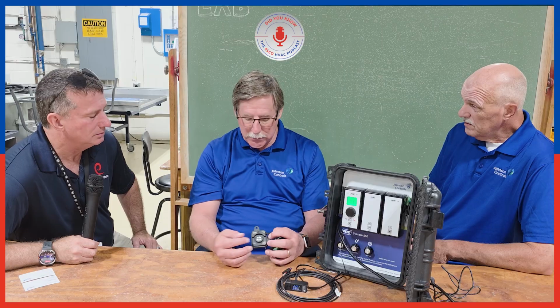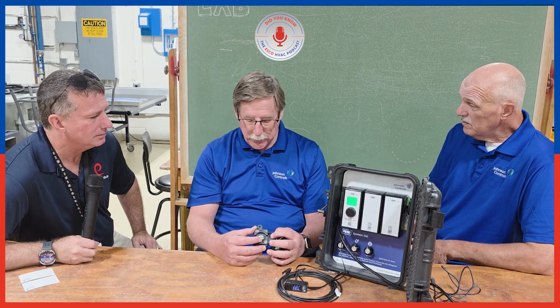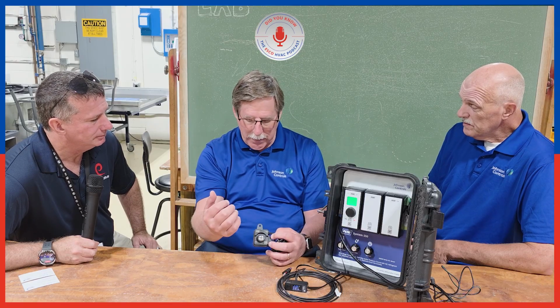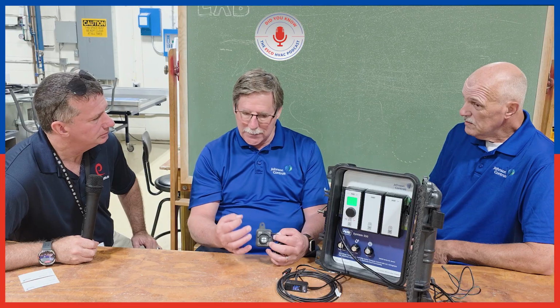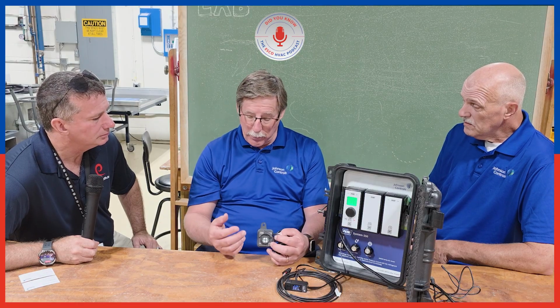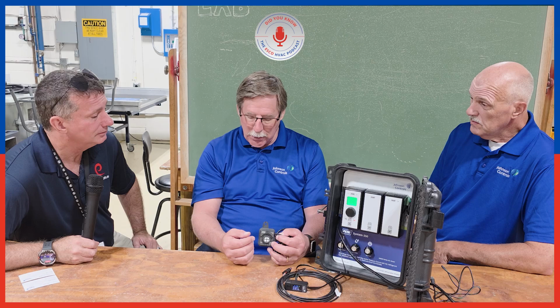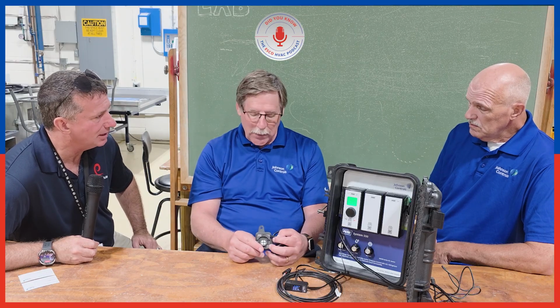So speed of sound, simply put, there are two stainless steel discs behind this hydrophobic screen. This hydrophobic screen allows gases to pass through, but sheds liquids. As that refrigerant leaks and the gas pools inside the sensor cavity, it's going to measure the sound wave, because part of UL 60335 is that it's self-monitoring. Every minute it checks its calibration against a temperature and humidity baseline. Why? Because speed of sound changes based on temperature and humidity. So it's got a temperature and humidity sensor as well to compensate for changes in environmental conditions. Not only that, but it has a countdown.